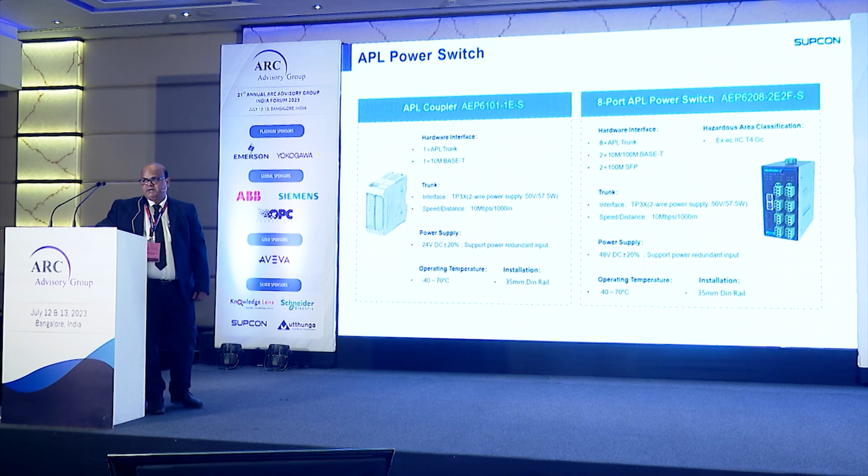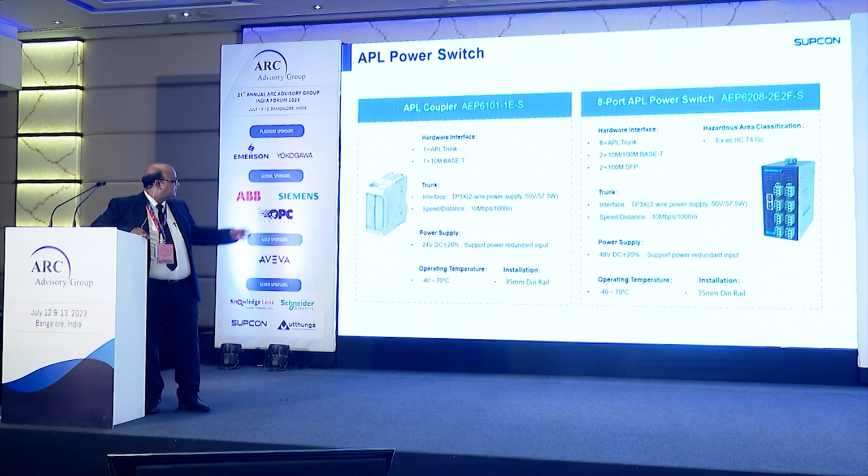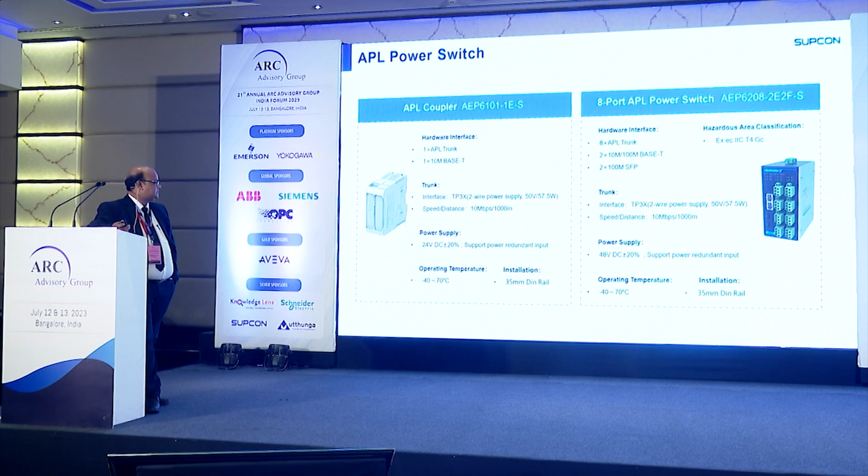So this is the APL power switch. The APL coupler is the hardware that can connect one APL trunk. It is used in the intrinsically safe environment, with hazardous area classification Ex ec IIC T4 Gc. 8 APL trunks can be connected to the 8-port APL power switch.